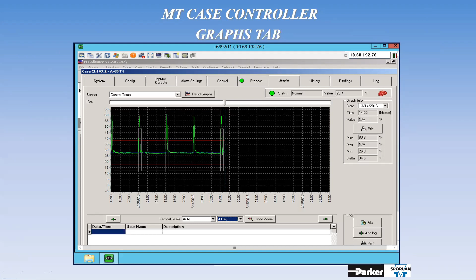All right, the other 700 series that we have, the first one we came out with was the monitoring node. And what I want to point out here is in about the same space as a 504 that could give me only 8 universal inputs, I now get 18 universal inputs out of this, okay? But here's the big takeaway, 24 volts AC. It is a standard transformer that you can get out of any electrical or refrigeration supply store. That it no longer has to be center tap.